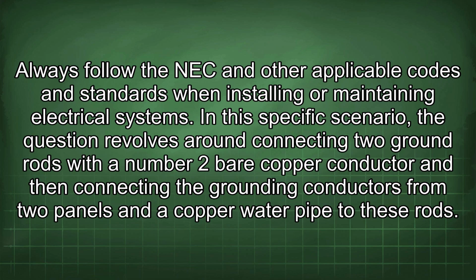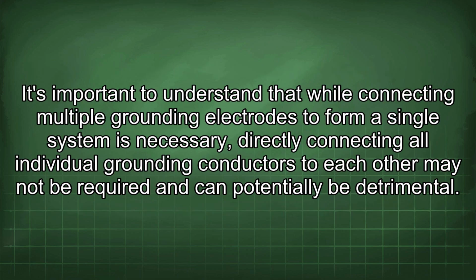In this specific scenario, the question revolves around connecting two ground rods with a number 2 bare copper conductor and then connecting the grounding conductors from two panels and a copper water pipe to these rods. It's important to understand that while connecting multiple grounding electrodes to form a single system is necessary, directly connecting all individual grounding conductors to each other may not be required and can potentially be detrimental.